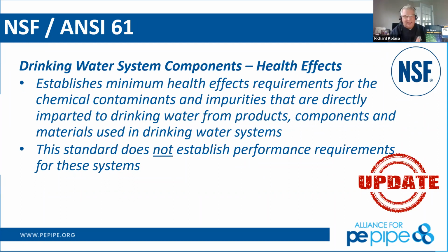And they've tested it in extreme conditions. They tested at 90 degrees Celsius, for all you non-Canadians and non-metric people, that's about 194 degrees Fahrenheit, for over 32 days. They let that water sit stagnant in that pipe. And then they give us a result back that says, here are all the items that we look for, and here are all the items we detected.